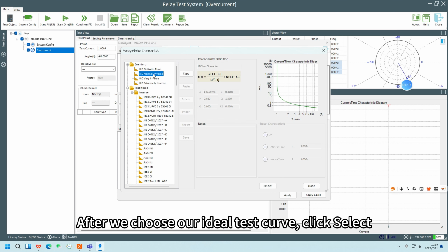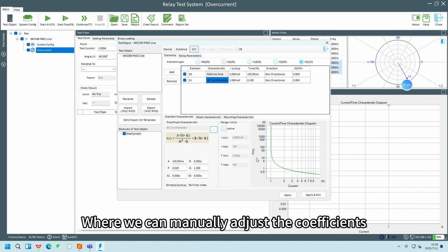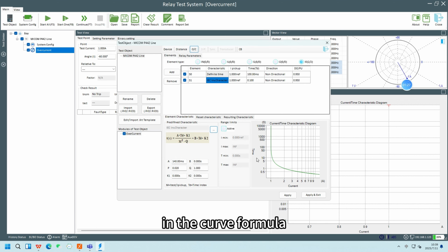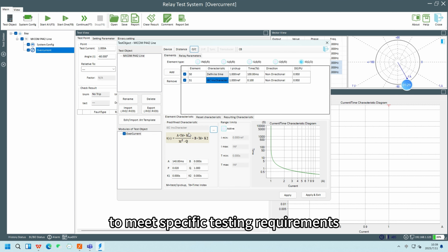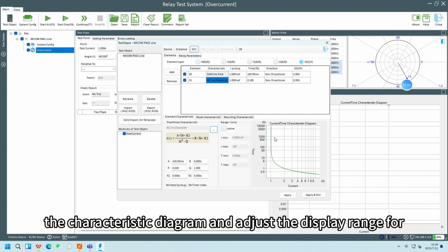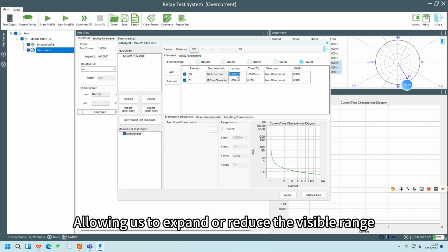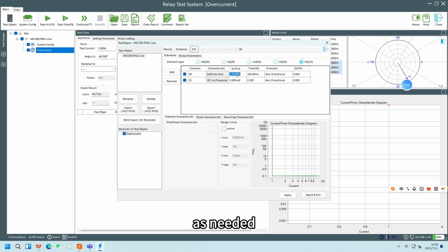After we choose our ideal test curve, click Select. Let's move to the settings below, where we can manually adjust the coefficients in the curve formula to meet specific testing requirements. Here, we can also see the preview of the characteristic diagram and adjust the display range for time limits within the boundary settings, allowing us to expand or reduce the visible range as needed.